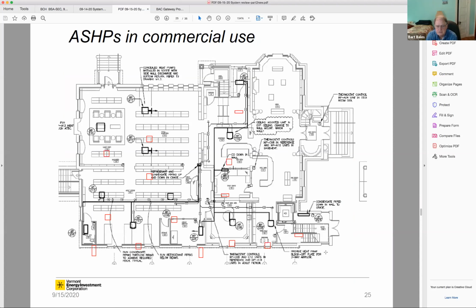So next slide. Just to show, you can have these heat pump heads spread all over the place in the building, the black boxes. And something that you may not be aware of is with something called variable refrigerant flow systems, you can have some of these units delivering heating and some of them delivering cooling at the same time, even though they're hooked to the same condensers. And that adds some added efficiency savings. It's in effect transferring energy from the overheated space to the space that needs heat.